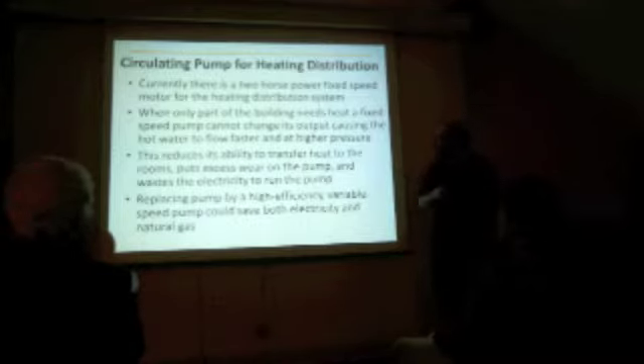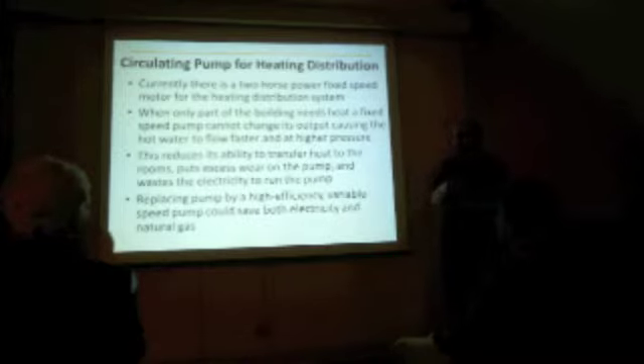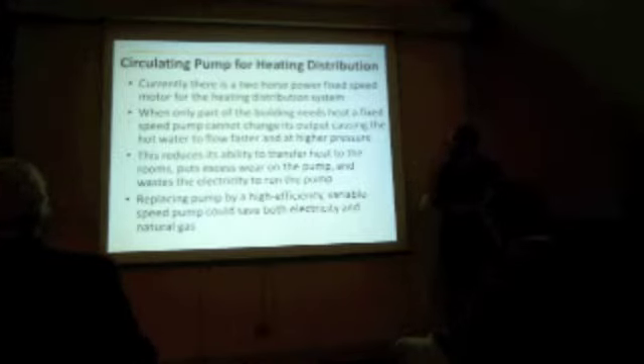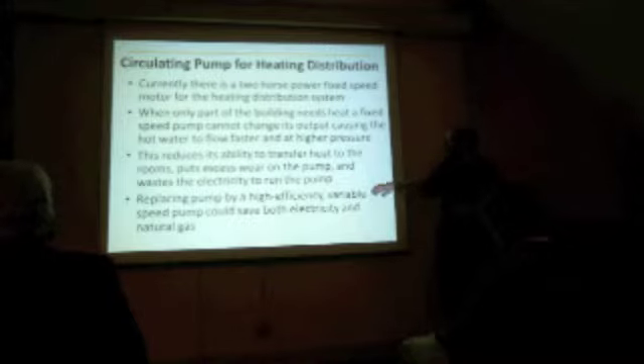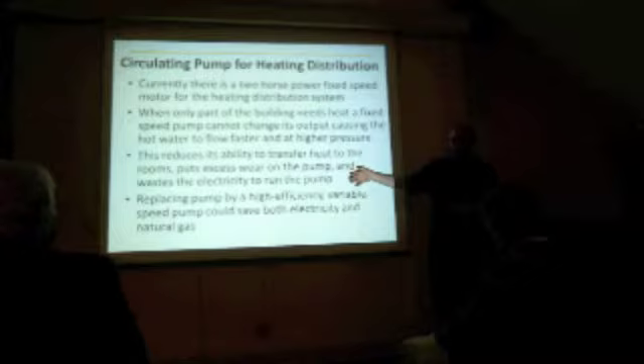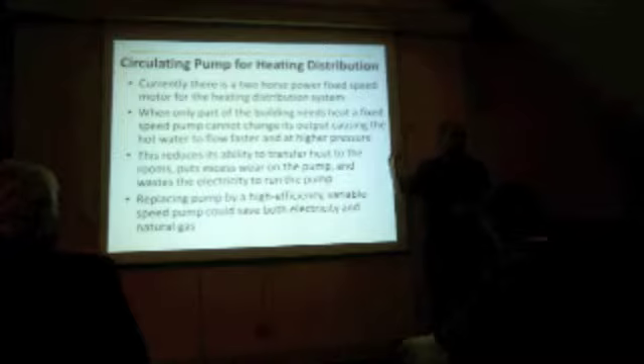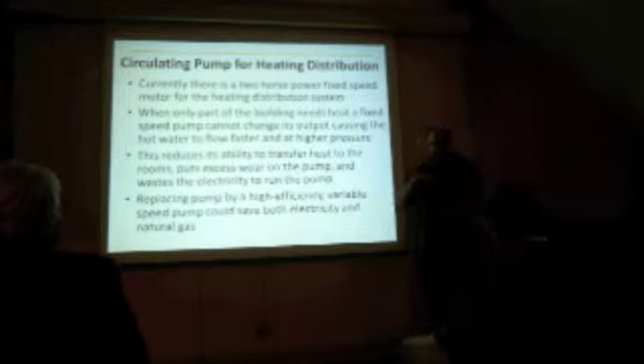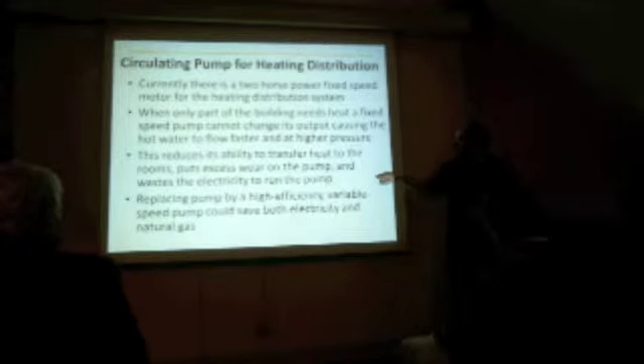So when only part of the building needs heat, two things happen. That motor kicks on, so it's actually moving the water faster through the rest of the system because the shutoff valves have been closed in the other parts, and it's raising the pressure. And that does two things. One, it needlessly uses the pump's energy to move that water when it wasn't needed, but it also means that the water that's supposed to heat the other spaces goes zipping through the heating system much faster, so it actually leaves less heat behind in the other part of the building. And you saw how much it was heating up. It was 130 some degrees. It puts excess wear on the pumps.